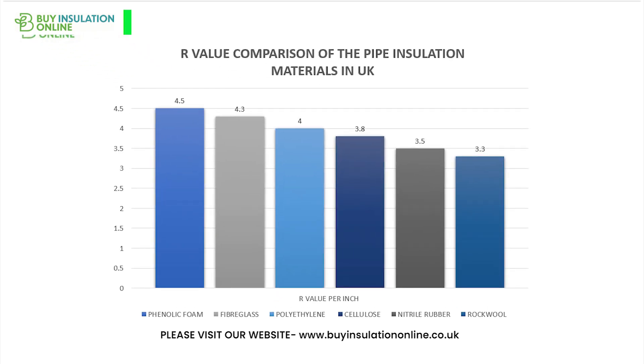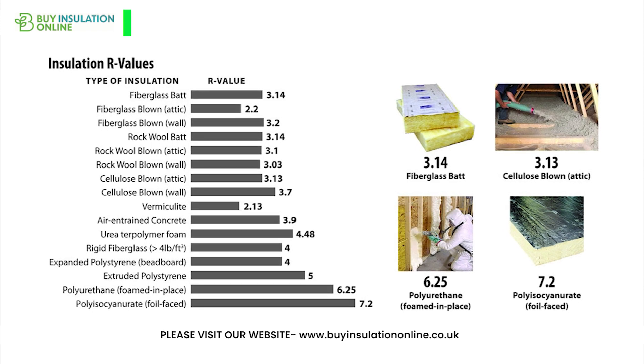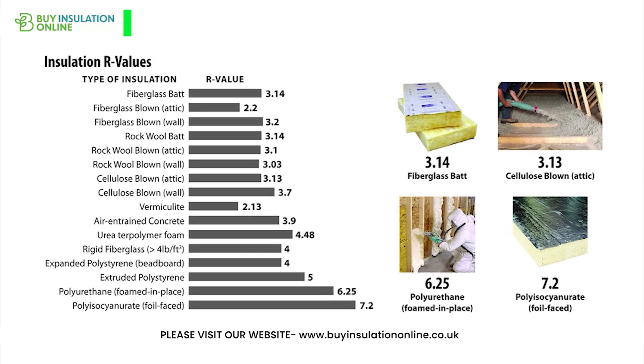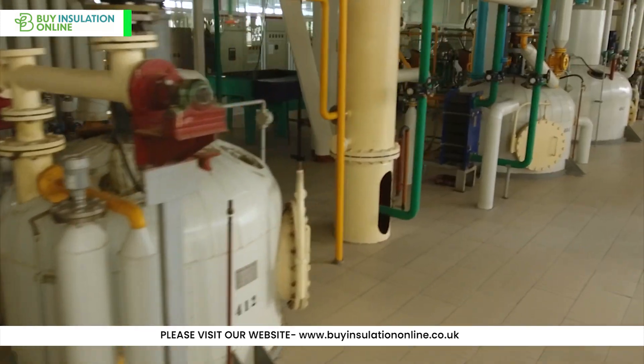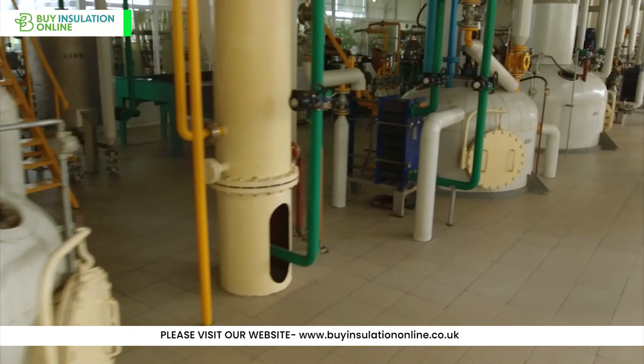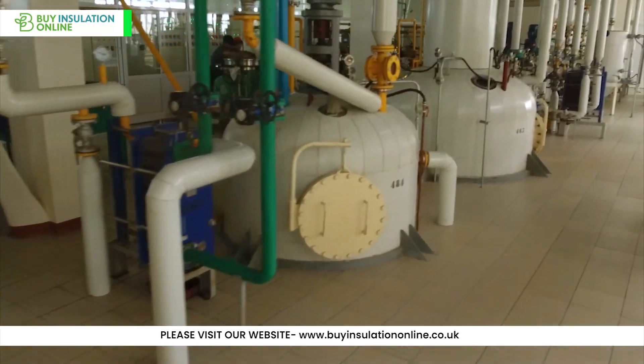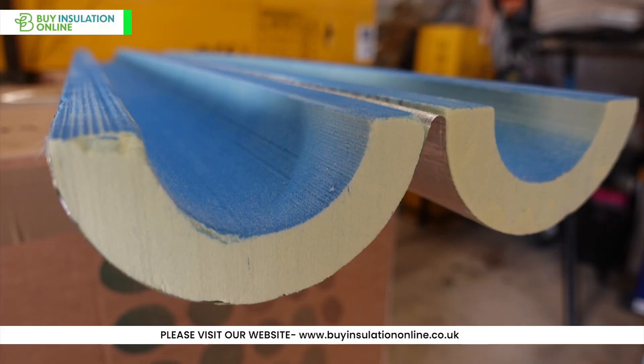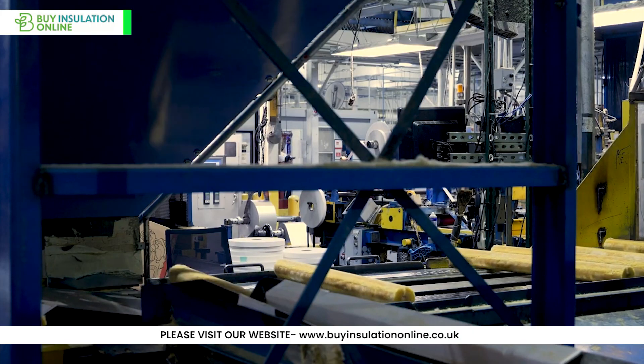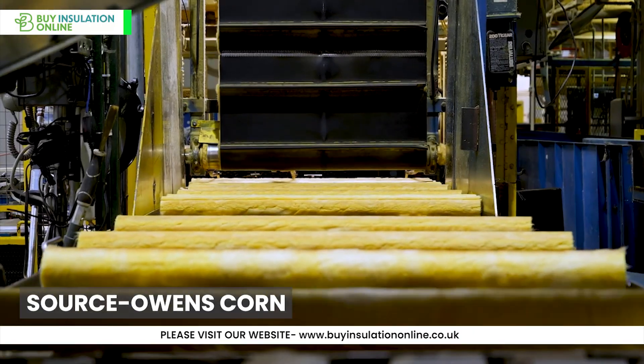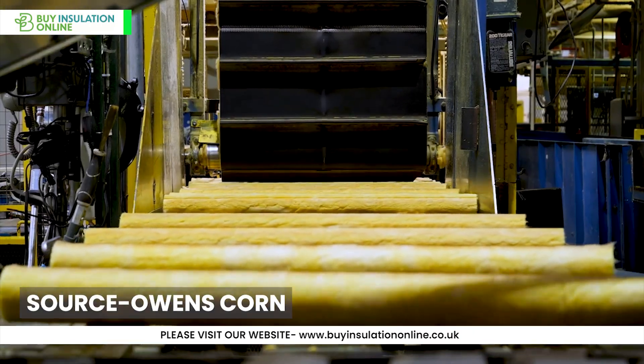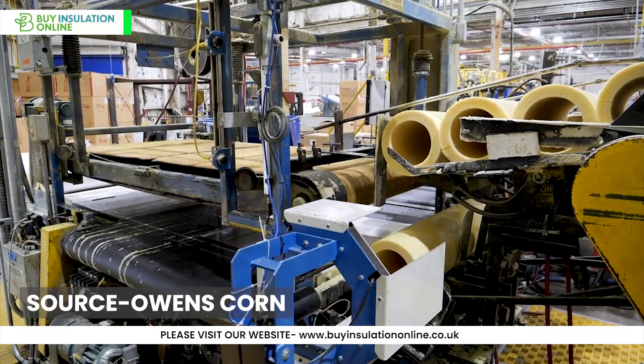This is converse to the r value, where a higher number means better insulation. However, r value is rarely used in the UK to measure pipe insulation performance. The k value of a material can be determined through laboratory testing and is often used to compare the thermal performance of different insulation materials. Manufacturers will have conducted these tests, which are verified by third parties, which allows us to know their k value.